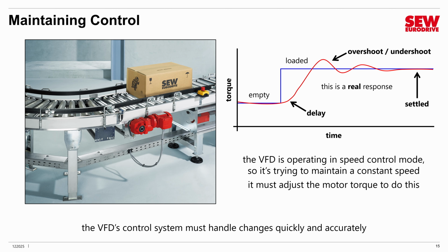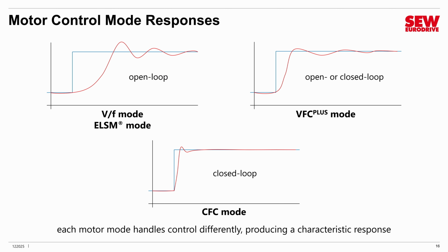This comes back to our motor modes. Different motor control modes handle this situation differently, and each one has a characteristic response. VF mode and ELSM, which are both open loop modes, they take a while to handle changes. VFC Plus, on the other hand, it does a better job. You notice it locks onto the new conditions pretty quickly. And CFC mode, as you can see, is excellent. It handles changes very quickly and accurately.